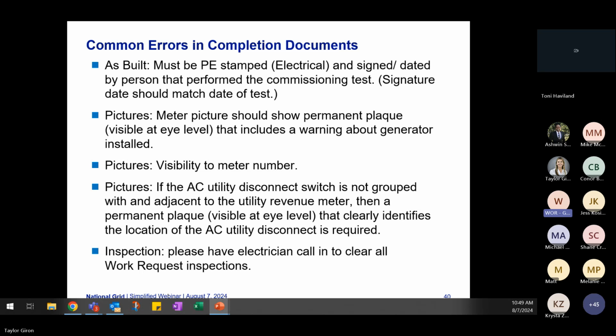The as-built also should be PE stamped, signed and dated by the person that performed the commissioning test. Dates and signatures should match. Our picture should show a permanent plaque that includes a warning about the generator installed. For the pictures, it's very important that we are able to read the meter number when we're looking at a meter. With the AC disconnect, if the switch is not grouped and it's not adjacent to the utility revenue meter, please put a plaque there that locates where at the facility the production meter is, so that emergency and National Grid personnel can get to it.